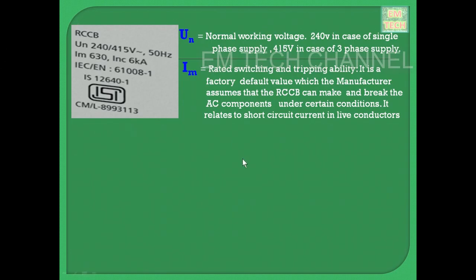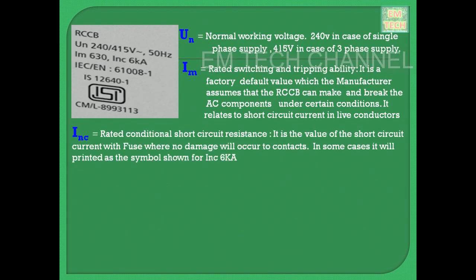Next, INC. INC is the rated conditional short circuit resistance. It is the value of the short circuit current with backup fuse where no damage will occur to contacts. In some cases, it will be printed as the symbol shown also. In some RCCBs, it will be mentioned as INC. In some RCCBs, the symbol will be provided, meaning the RCCB has to be provided with a backup fuse, and the RCCB short circuit resistance is 6000 amps, that is 6K.